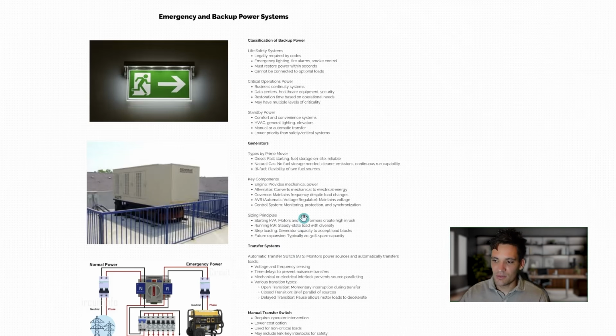They'll have a governor, which controls the speed and frequency, so it operates at the same 50 hertz or 60 hertz or whatever your grid operates at. They'll have some sort of voltage regulation to standardize the level of voltage being produced, and they'll have some sort of control system which allows either synchronization with the grid, or if they're standalone power systems, will ensure that they operate smoothly for the loads that are connected to them.